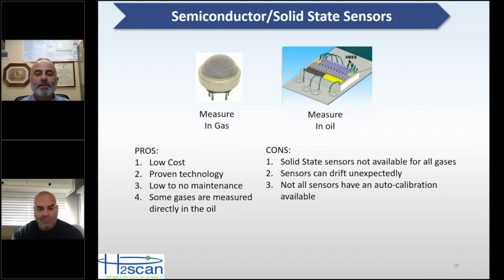Sensors can drift unexpectedly. So if you have a photoacoustic monitor, say with a separate hydrogen or oxygen sensor, chances are, from my understanding, most of the time, if those sensors start drifting, there's no way to know that the sensor is drifting other than comparing it to an oil sample. And so there's no internal way to auto-calibrate. Some of the sensors do have an auto-calibration or some sort of way to check the calibration in real time. And so those sensors are, of course, preferred because you don't have to worry about the calibration over time.